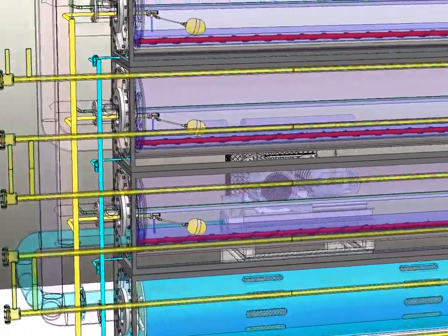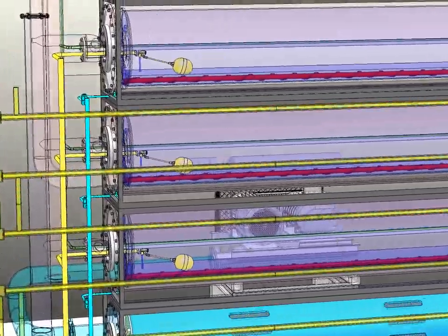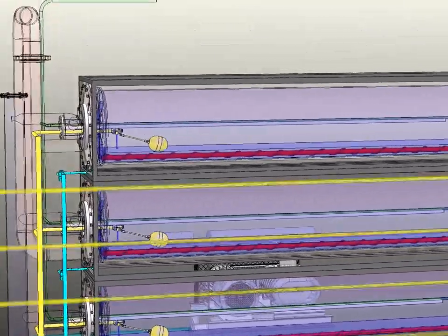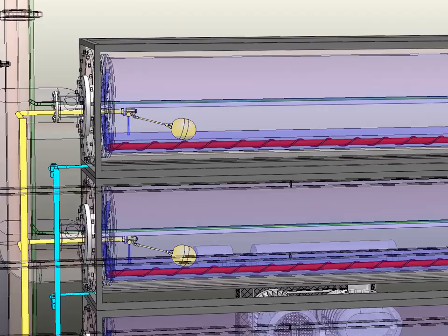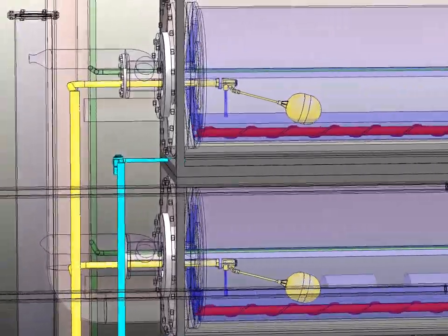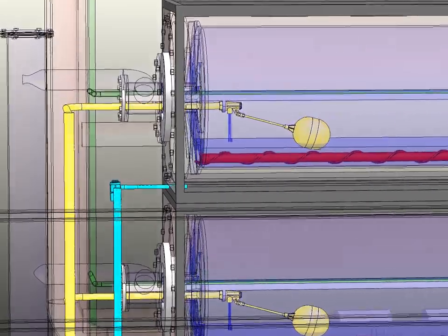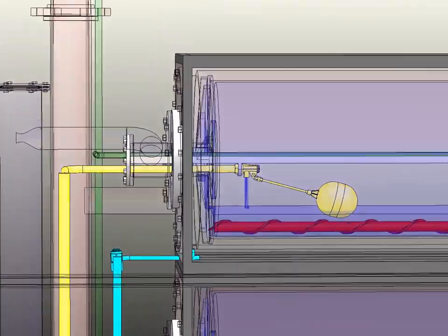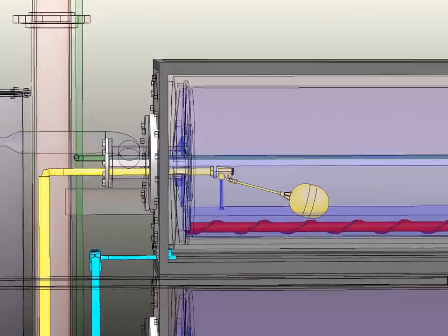The evaporator allows the concentration of solutions to high salinity values, at which precipitates and colloidal particles begin to form. It is colloidal particles in contact with the heating surface that gradually degenerate into solid layers of scale, which impede heat transfer.